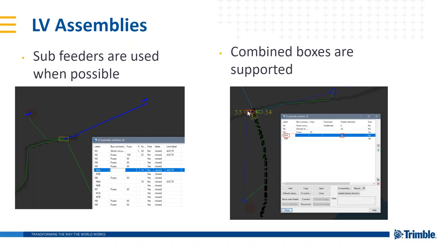One of the latest developments we've done with optimizer is called brownfield assemblies. With the ability to consider brownfield assemblies, optimizer explores how much free capacity each of the cable boxes included in the calculation has, and then it either keeps an existing cable box, or if needed and allowed, proposes a new cable box for some location where the lines that should be fitted just won't fit. Let's look at this use case next.